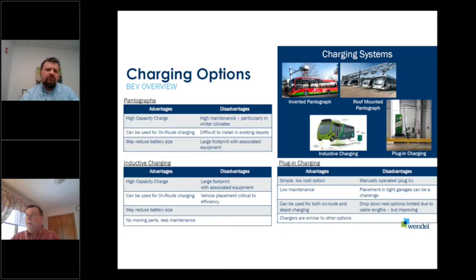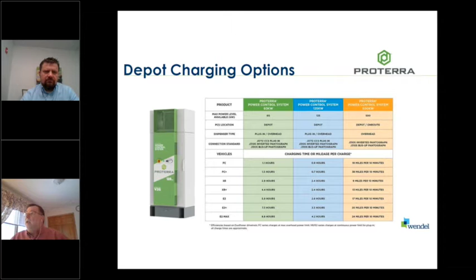Next slide. We have used a lot of Proterra chargers on some of our projects. The Proterra chargers come in three sizes for the Proterra buses: 60, 125, and 500 kW ranges. In depots we'll often use 60 to 125 kW depending on the timing of getting the fleet out, and en route is usually the 500 kW option.